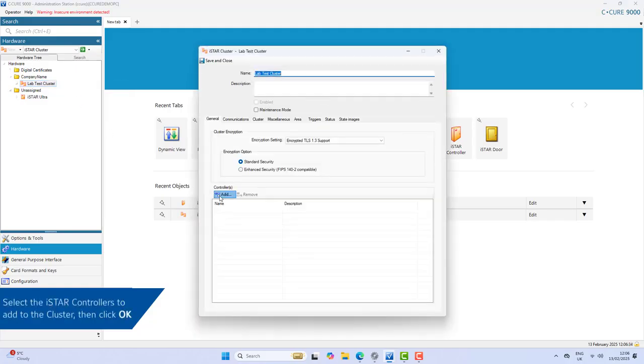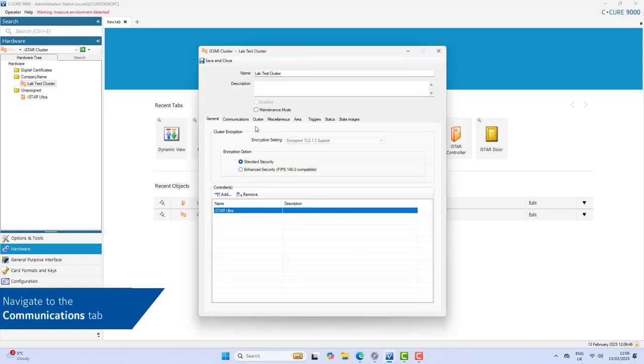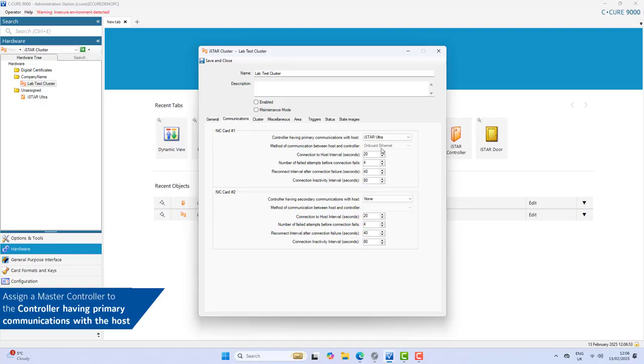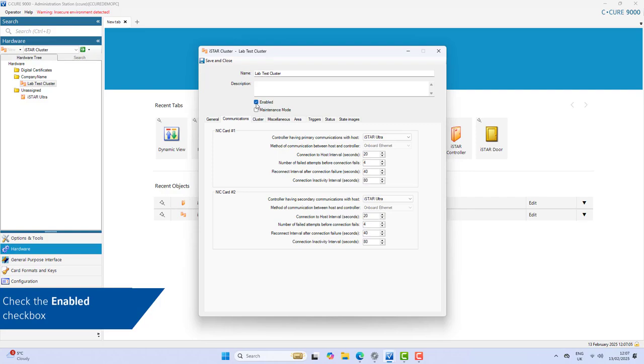Select the Communications tab. In a controller having primary communications with the host, assign a master iStar controller for the cluster. In a controller having secondary communications with the host, select the master iStar controller. To enable the cluster, select the Enabled checkbox, then click Save and Close.